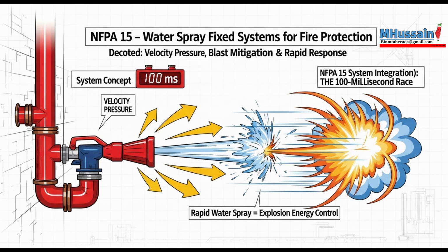At those speeds, the kinetic energy component, the PV, is pretty small, often negligible. But NFPA 15 systems are designed for massive instant deluge. Velocities can easily jump to 30 feet per second, maybe even 40 feet per second near the main riser. At those high speeds, ignoring PV leads to potentially huge errors in your pressure calculations.